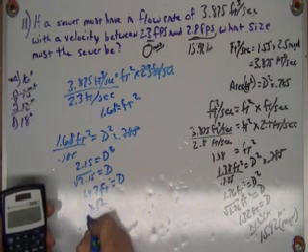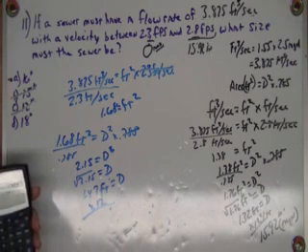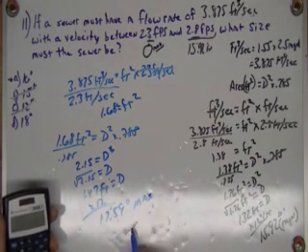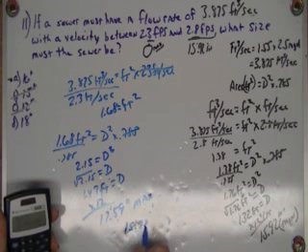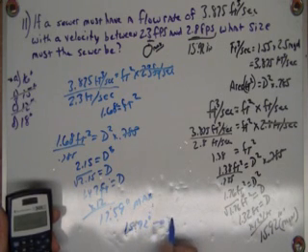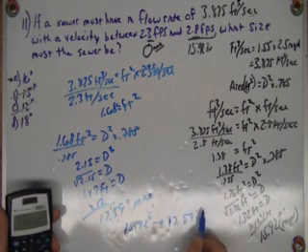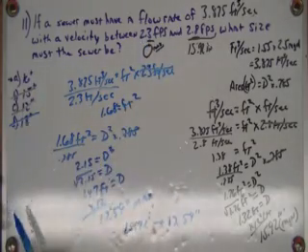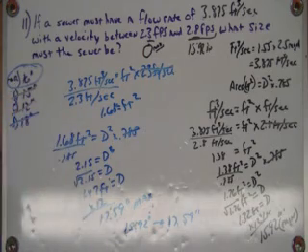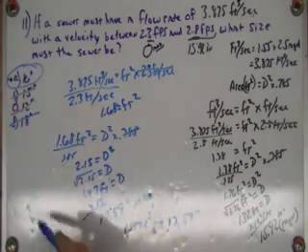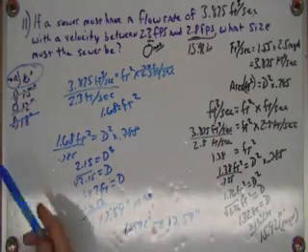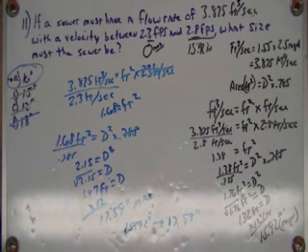So the valid pipe size range is 15.92 inches to 17.59 inches. An 18-inch pipe would be too big — the velocity would drop below 2.3 ft/s. The answer is 16 inches, as it falls within the required range. I rarely do the second part, but it's not a bad idea to verify. The answer is 16 inches.